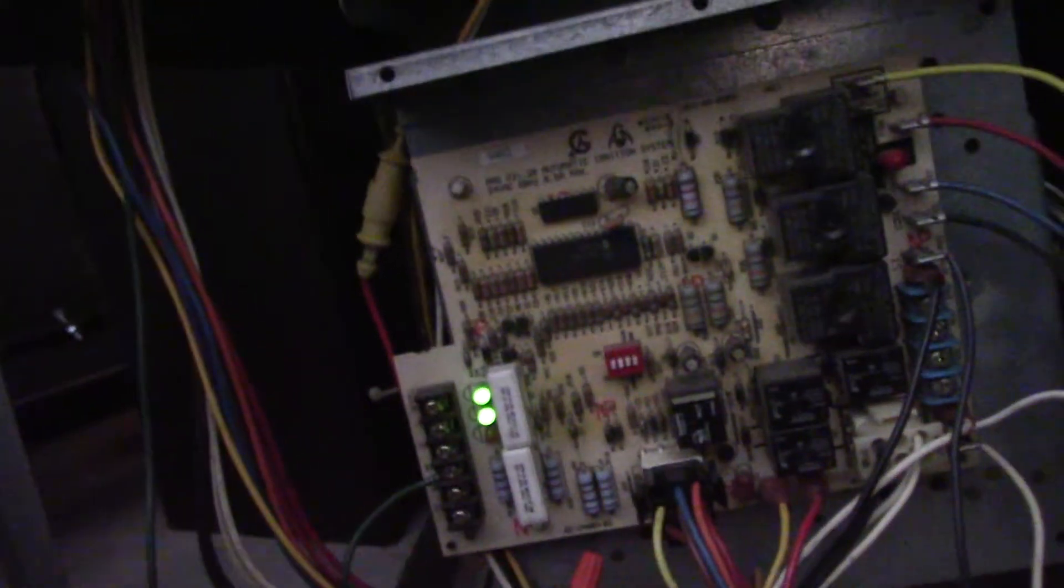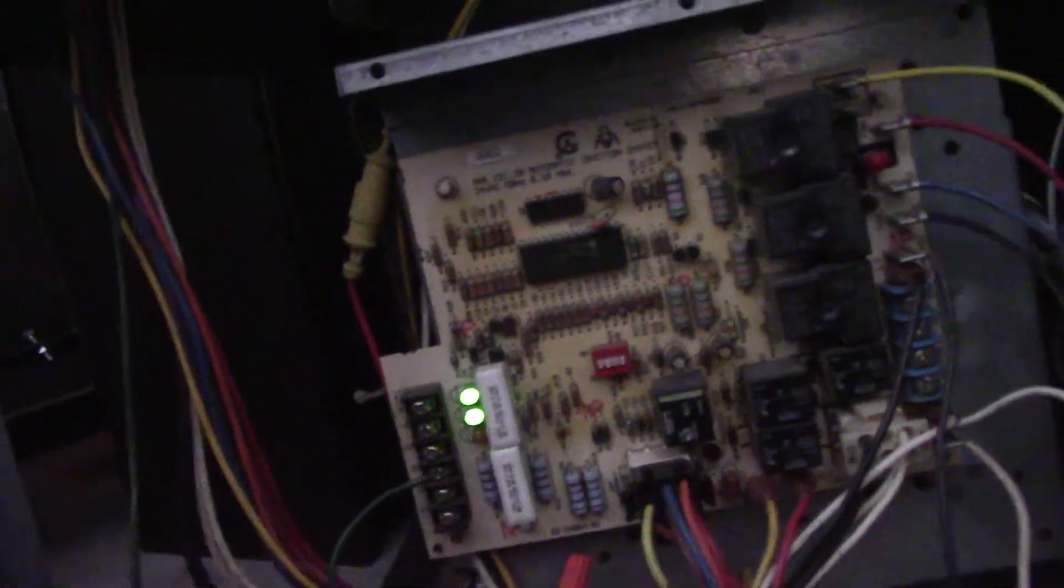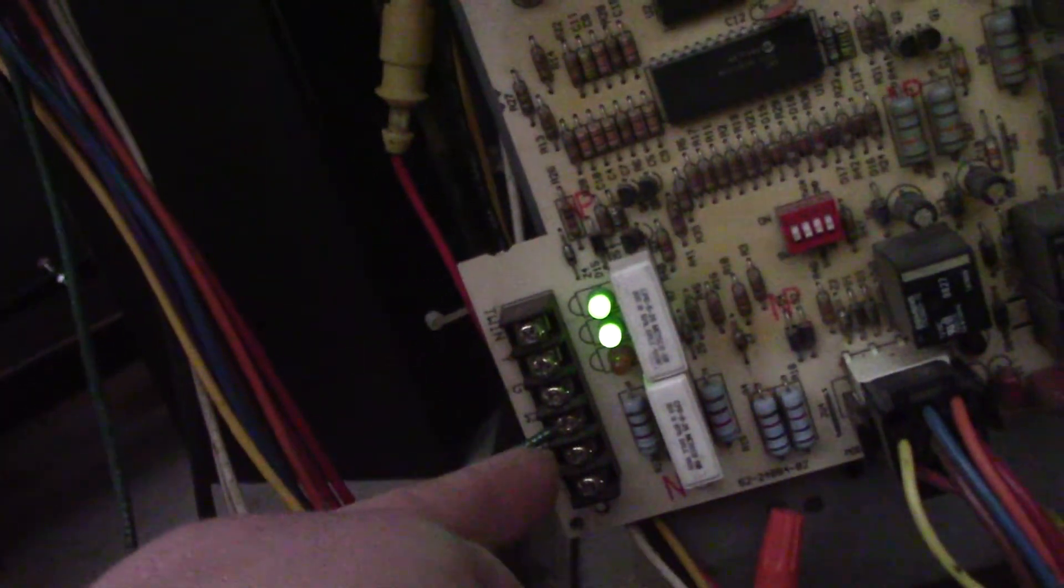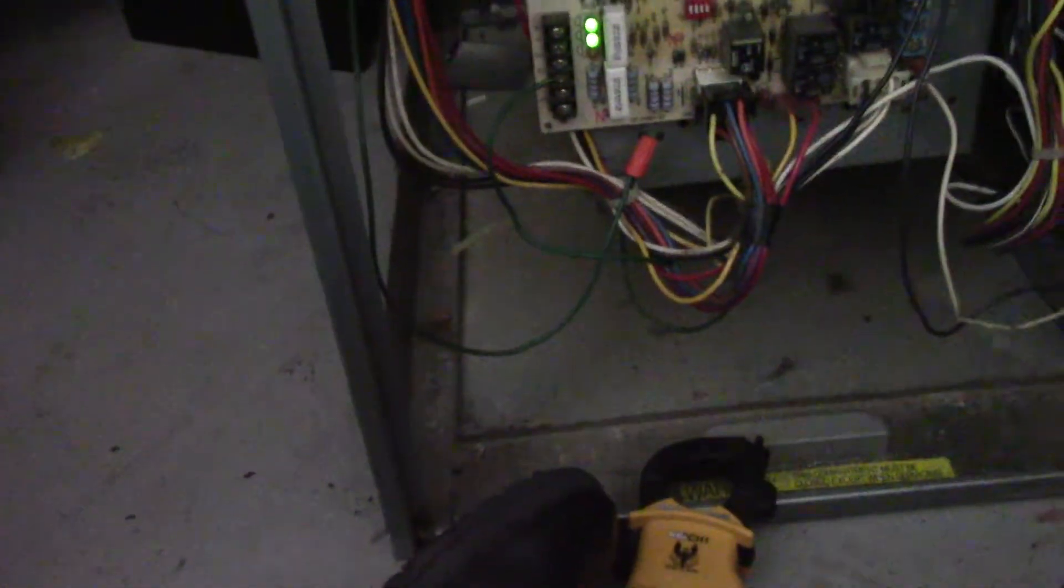You can disconnect R and W, tie them together, go upstairs to the thermostat and ohm it out. If you get OL, you've got broken thermostat wire and have to pull new wires through. If you have zero, you have a problem at the thermostat.